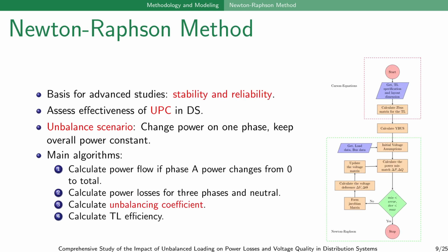Newton-Raphson, on the other hand, is a method widely used for power flow studies, providing the basics for more advanced stability and reliability analysis. In our study, this method is used to evaluate the effectiveness of the UPC in unbalanced distribution system. The main algorithm involved calculating the power flow, power losses, unbalanced coefficient, and transmission line efficiency under varying load conditions.